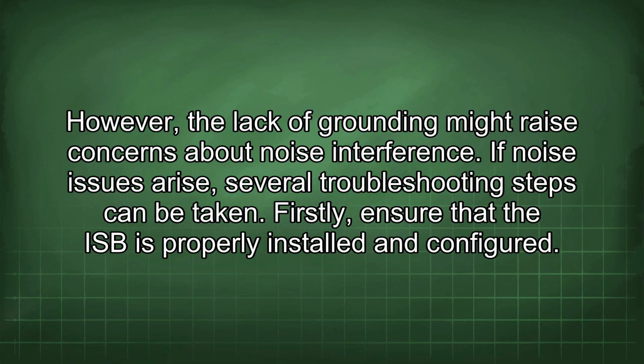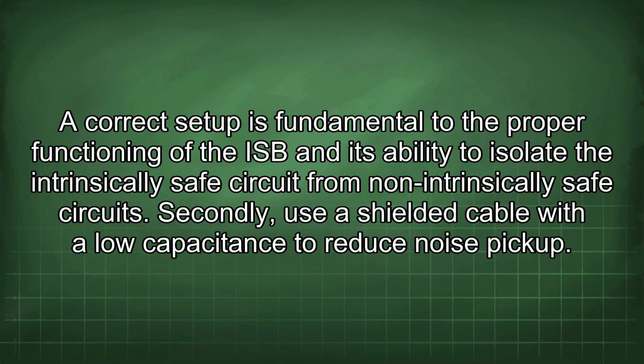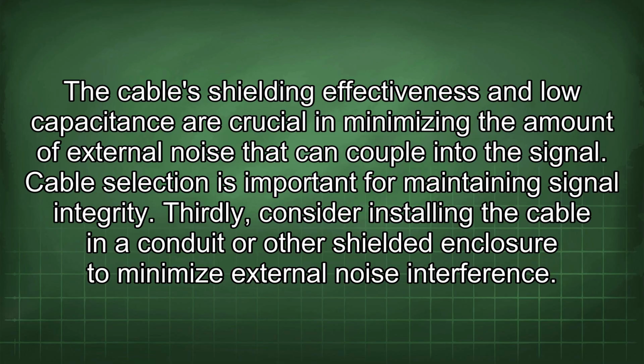Firstly, ensure that the ISB is properly installed and configured. A correct setup is fundamental to the proper functioning of the ISB and its ability to isolate the intrinsically safe circuit from non-intrinsically safe circuits. Secondly, use a shielded cable with a low capacitance to reduce noise pickup. The cable shielding effectiveness and low capacitance are crucial in minimizing the amount of external noise that can couple into the signal. Cable selection is important for maintaining signal integrity.